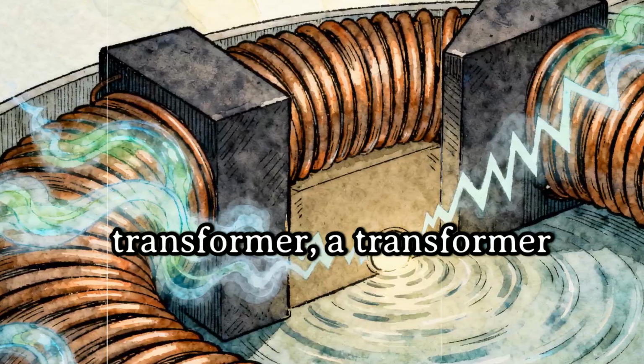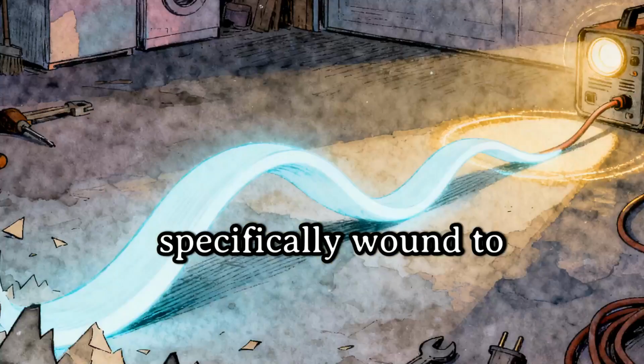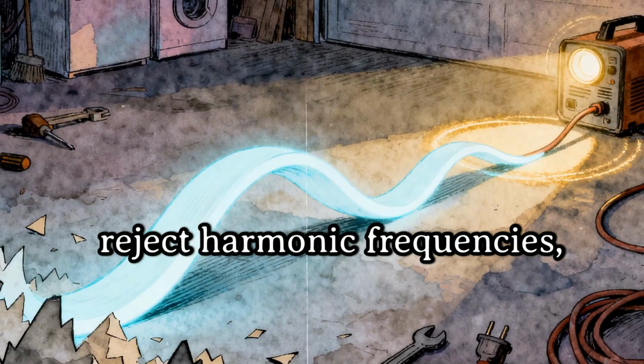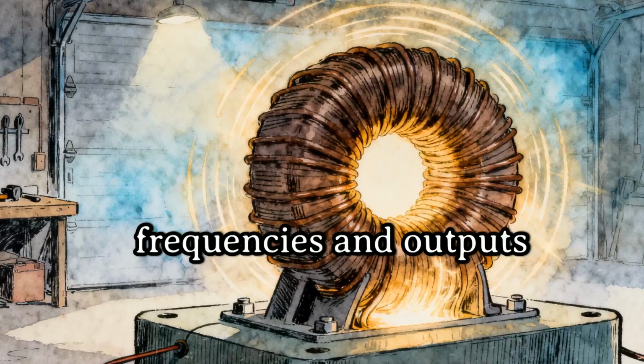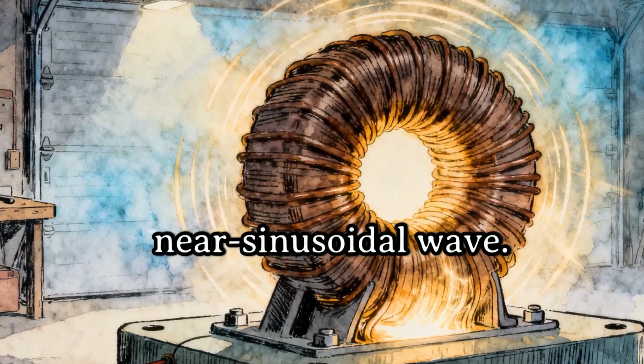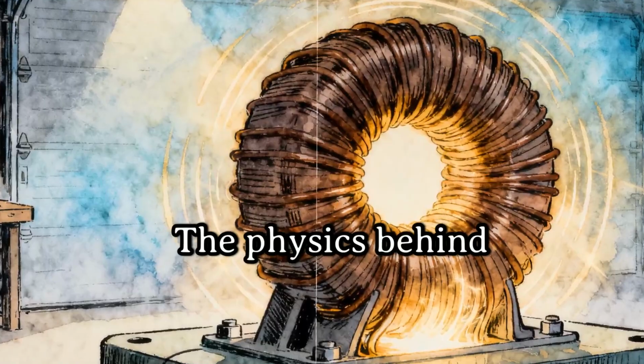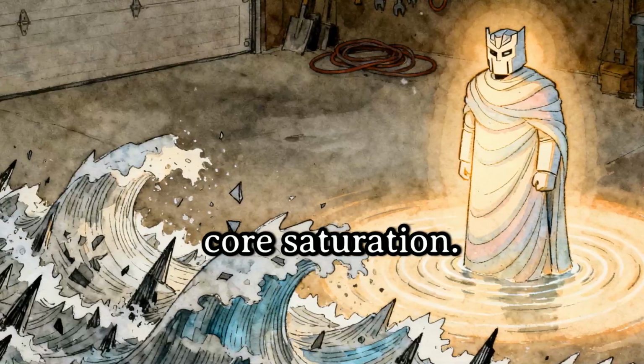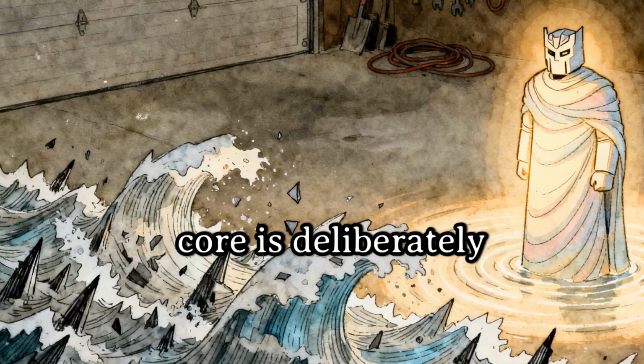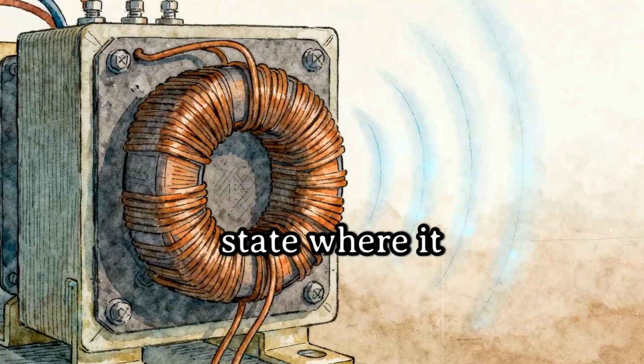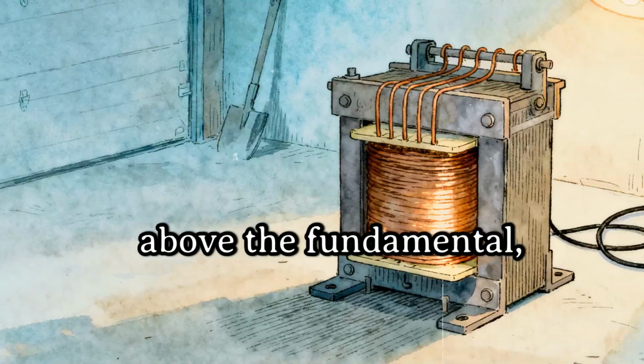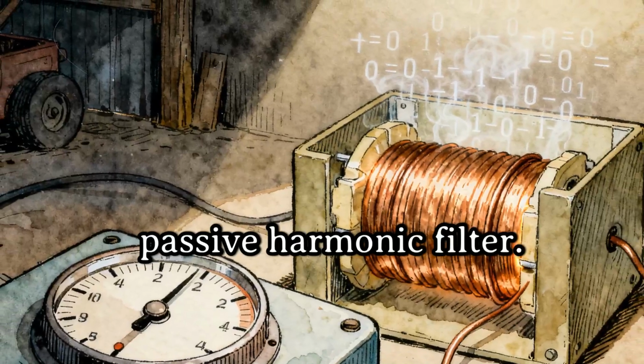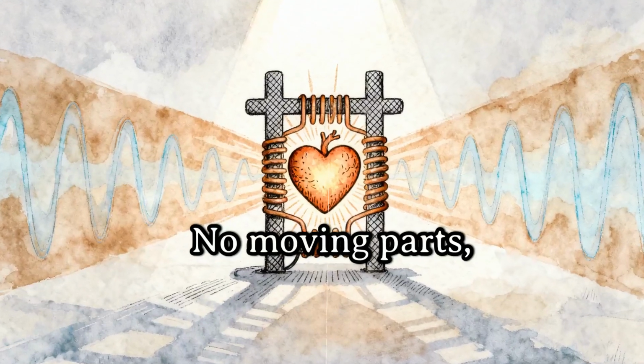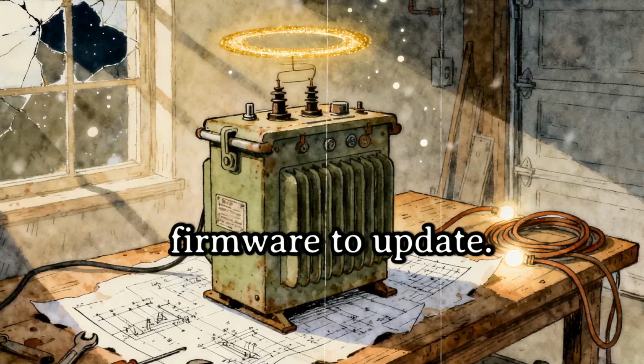Inside is a ferro-resonant transformer, a transformer specifically wound to reject harmonic frequencies, which absorbs the dirty frequencies and outputs a stabilized near-sinusoidal wave. The physics behind this involves magnetic core saturation. The transformer's iron core is deliberately driven into a state where it naturally attenuates frequencies above the fundamental, acting as a passive harmonic filter. No moving parts, no software, no firmware to update.